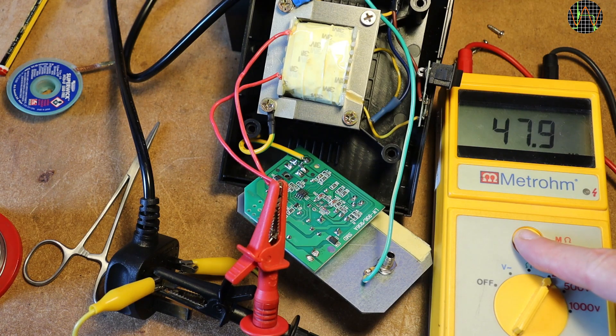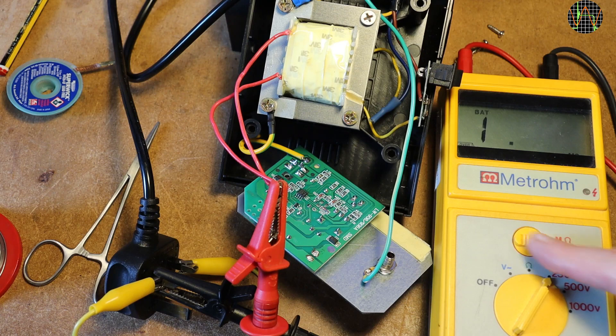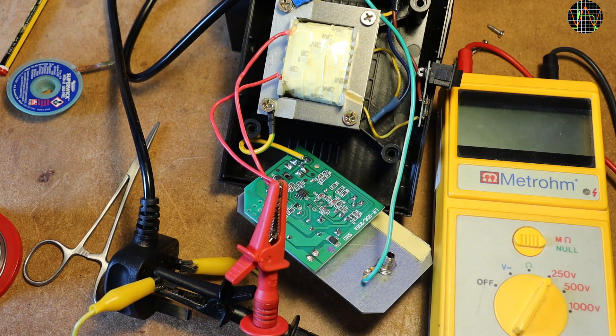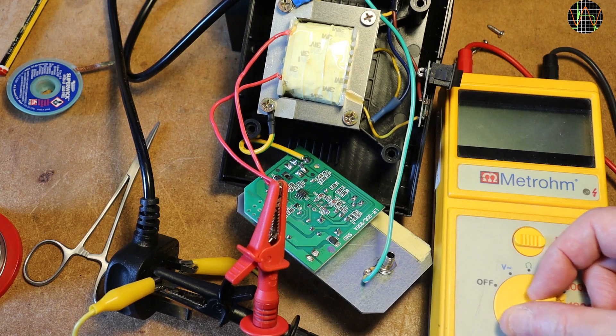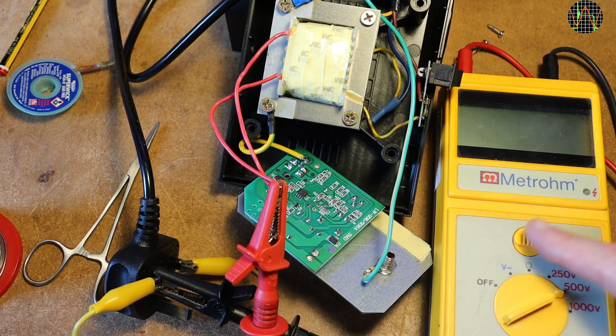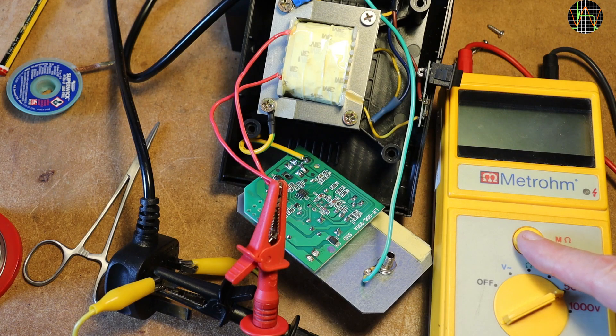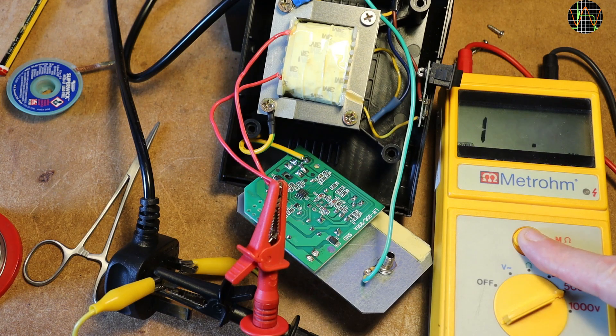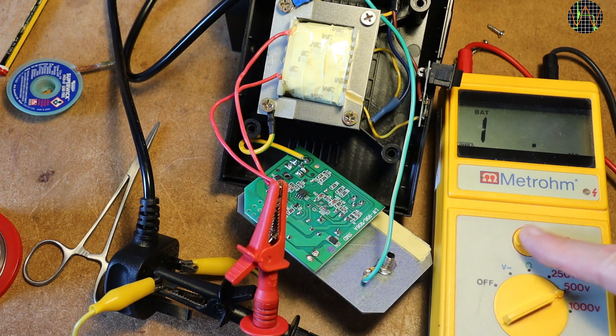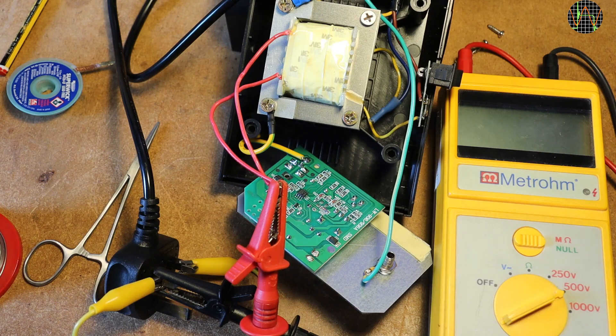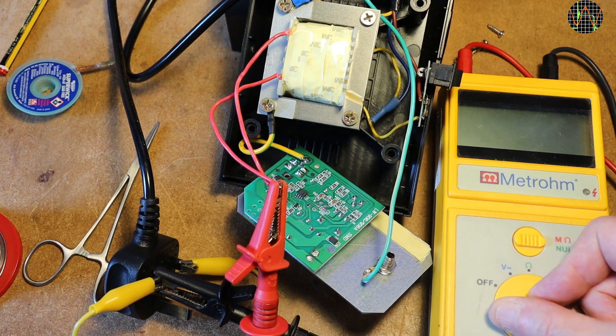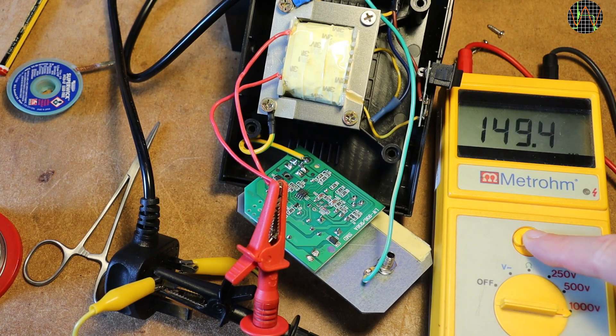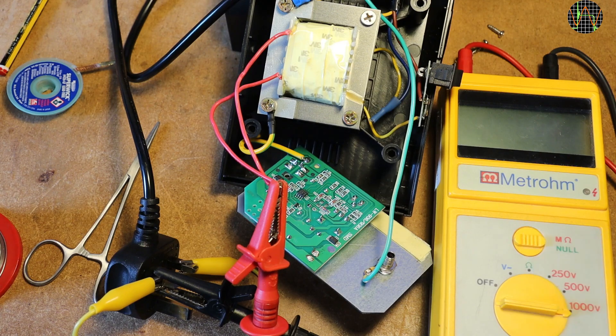250V, here it goes. This means no leakage at this voltage. Let's go to 500. No problem here as well. Will it handle 1000V between primary and secondary? Yes, everything fine, no worries here.